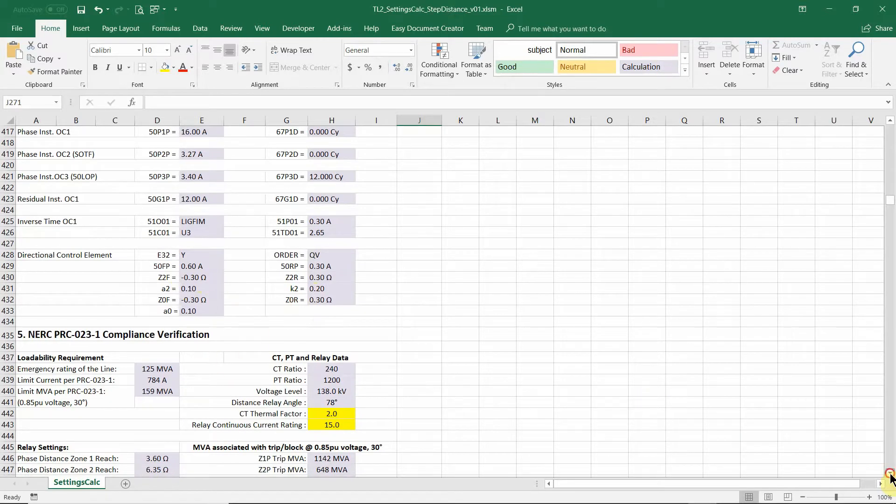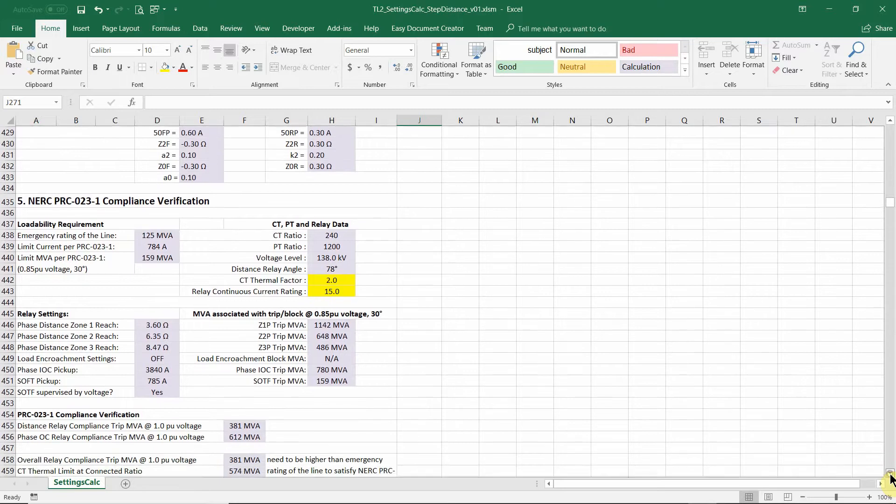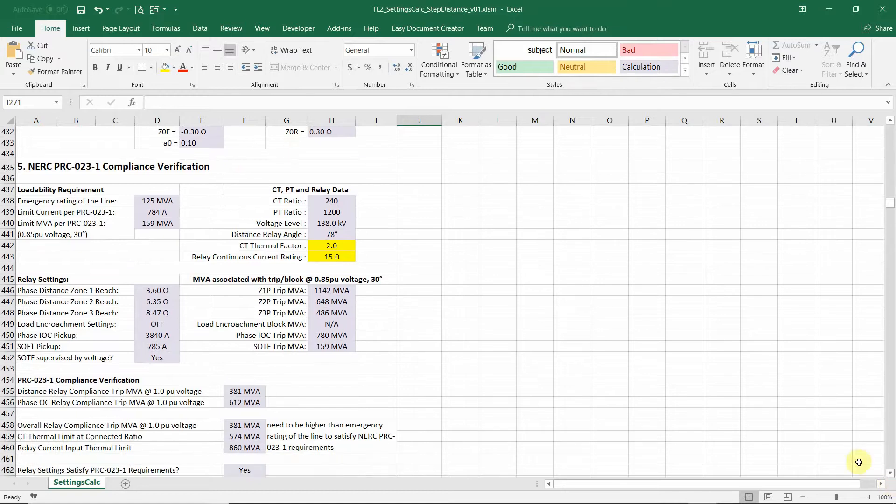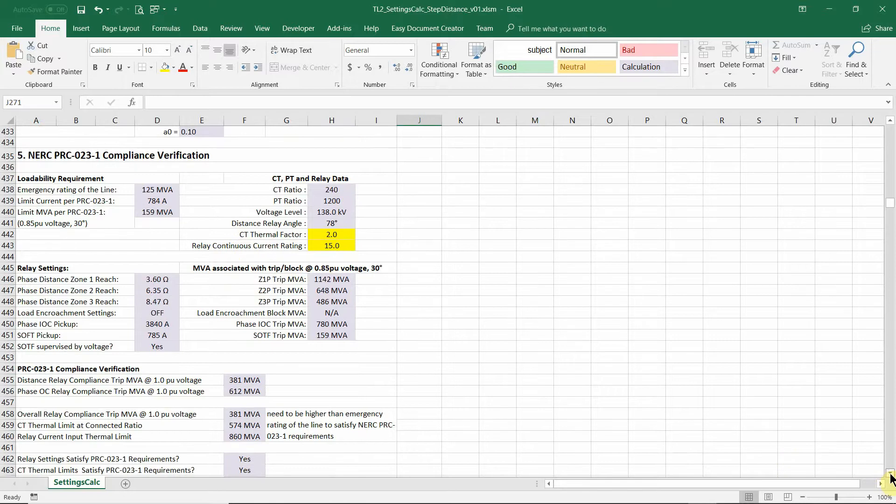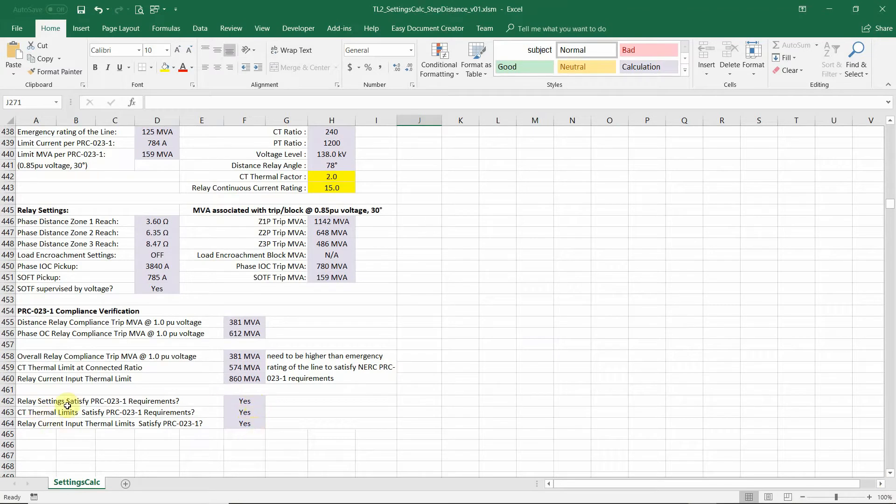And the section five is the NERC PRC 23 compliance verification part. You don't need to really change anything except the CT thermal factor or relay input current rating. In most cases, you don't need to change those. And after all this calculation, you can see the yes, yes, yes, yes.